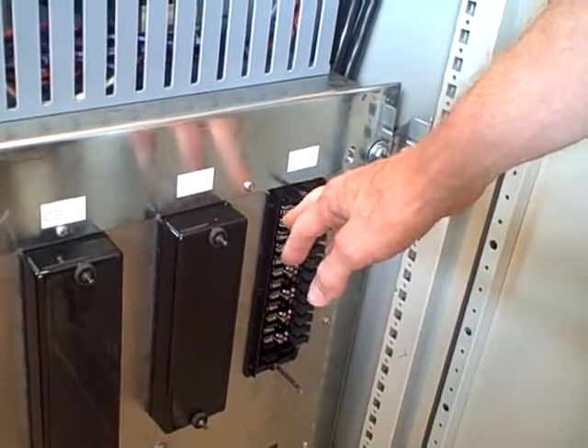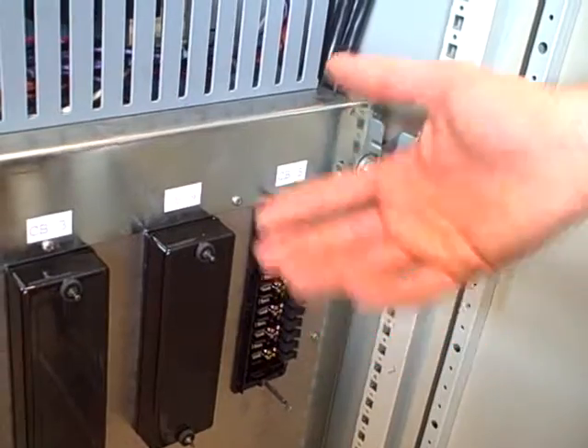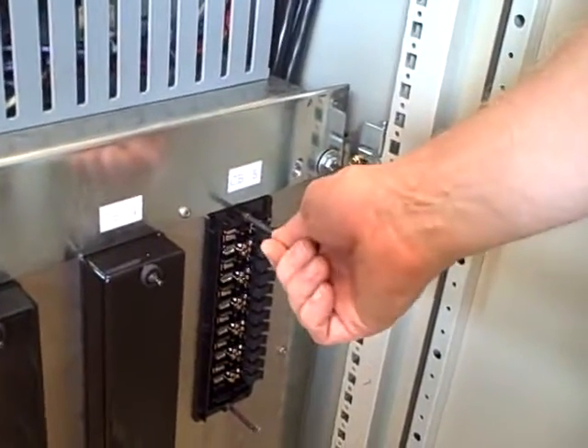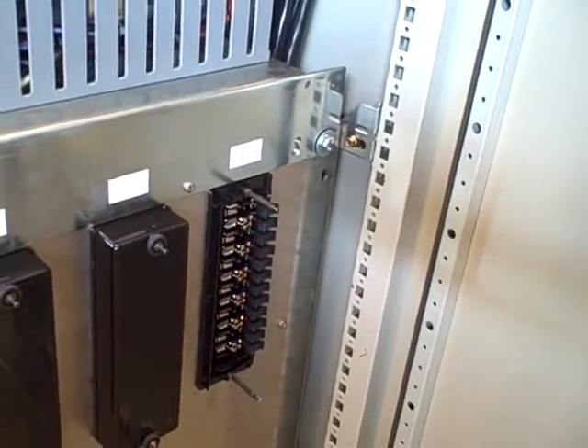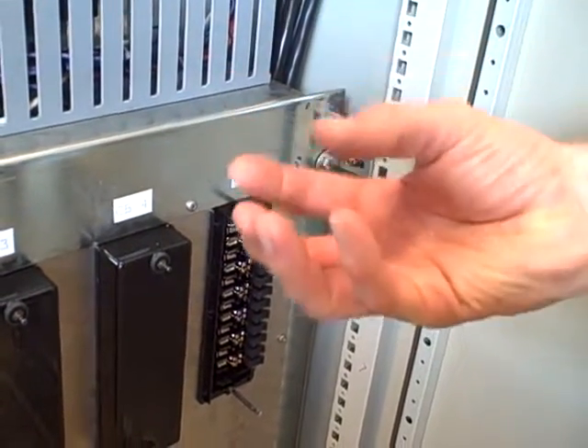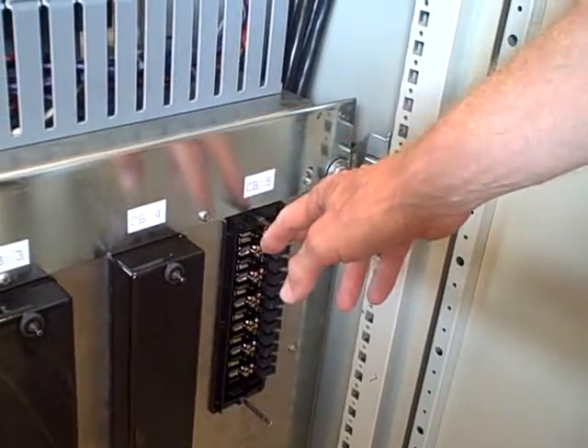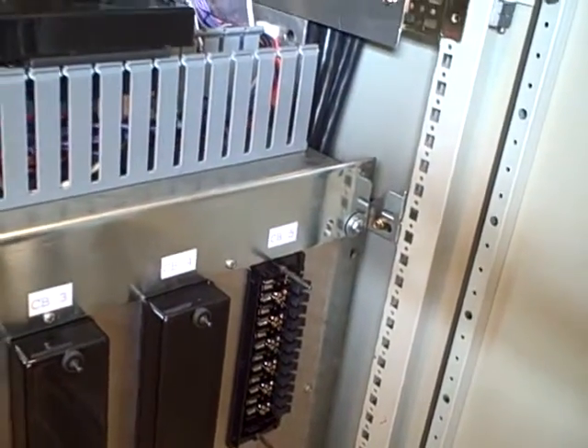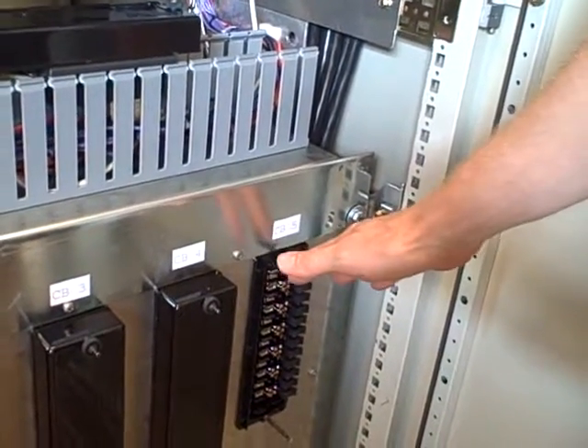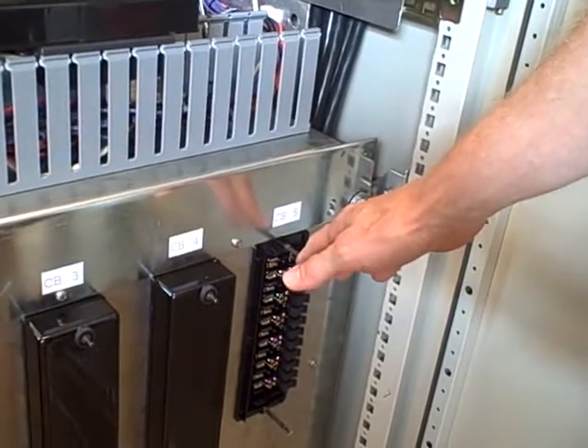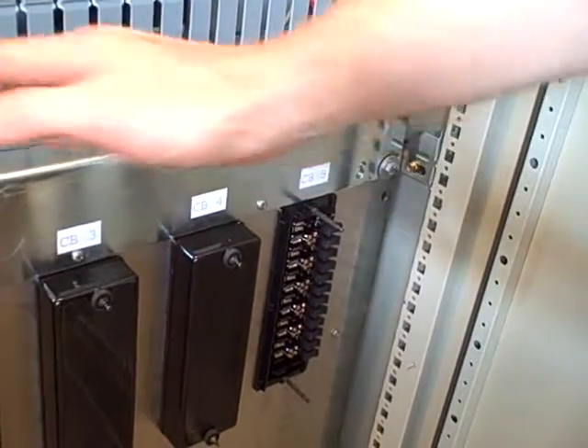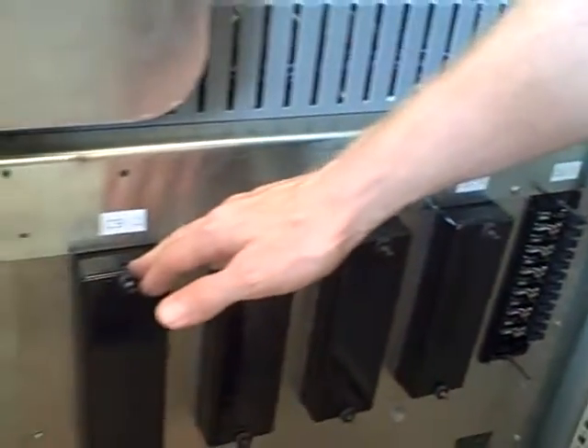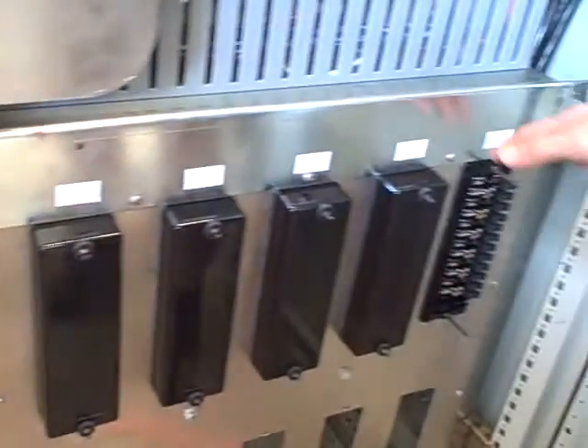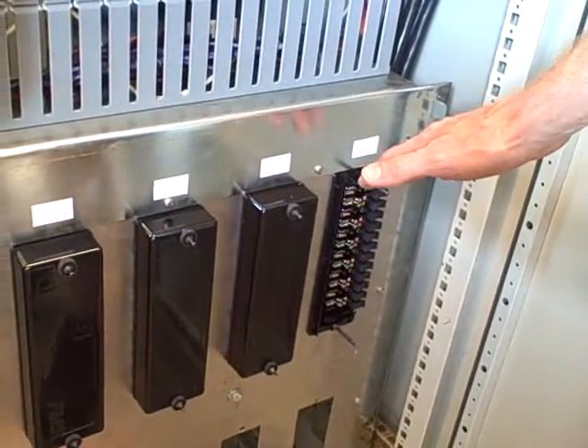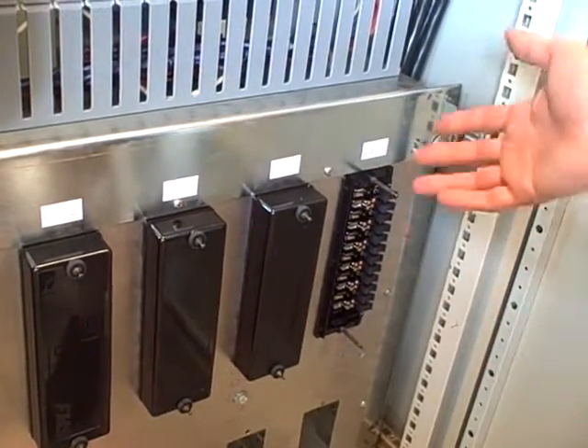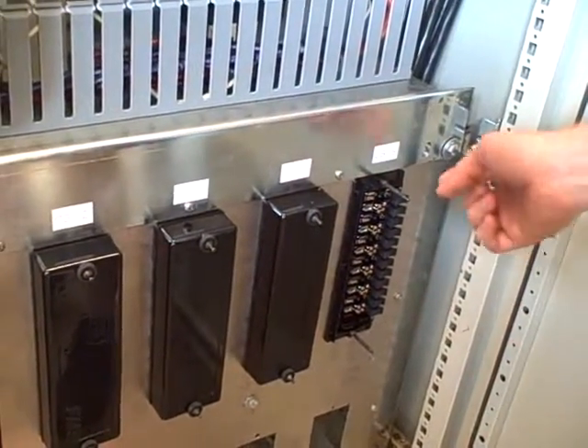Now this is a shorting switch, which you need to have in a CT circuit for safety reasons. So when I open that knife switch, it will place a short circuit on the CT side, so the CT itself never becomes open circuited, but it will disconnect that CT from our differential relay. So what's going to happen is our differential relay is going to think it sees a difference of current on A phase. It will see the current entering the bus through circuit breaker number 1 A phase, but it will not see the current exiting the bus through circuit breaker number 5 A phase. So I'll get a trip event, an 87 differential, as soon as I open this.